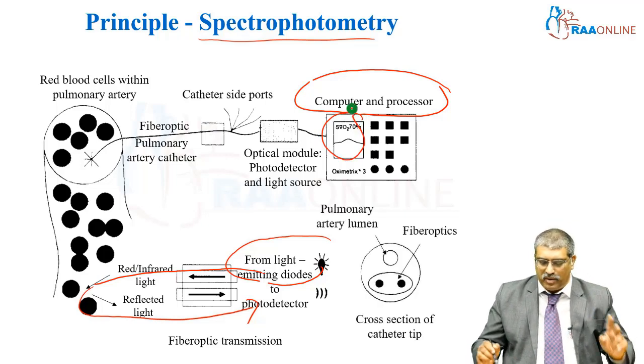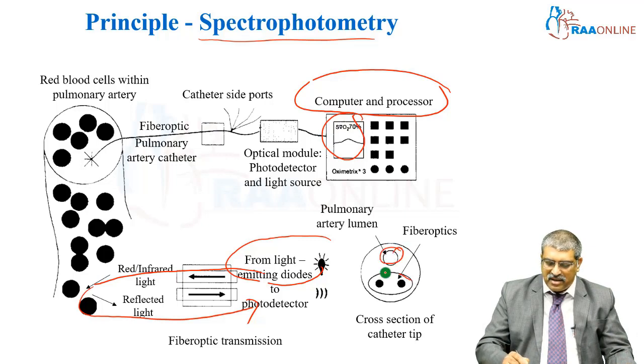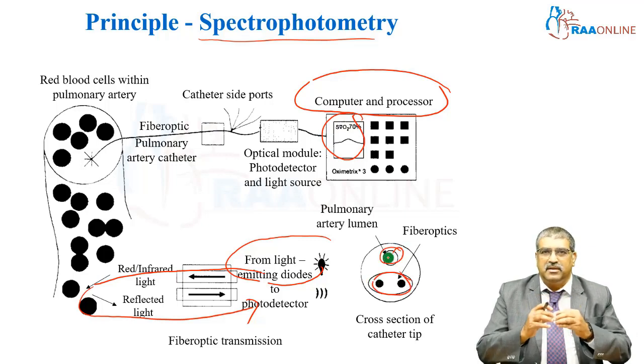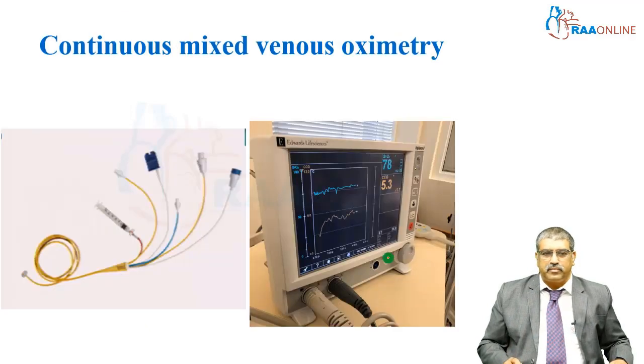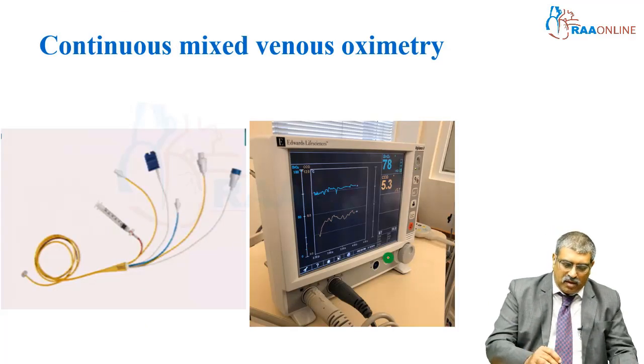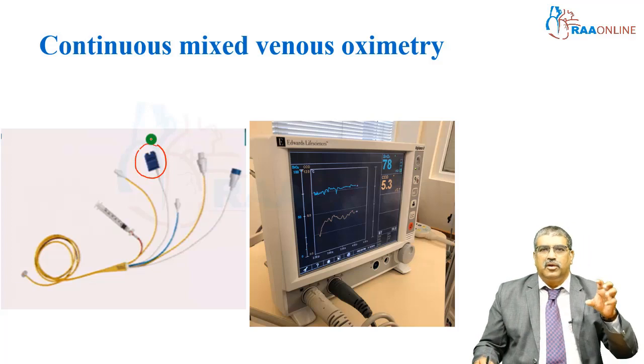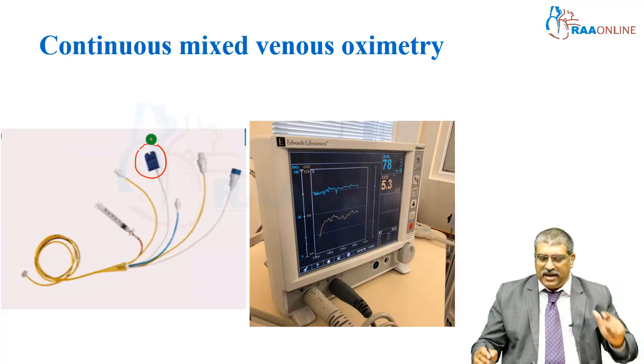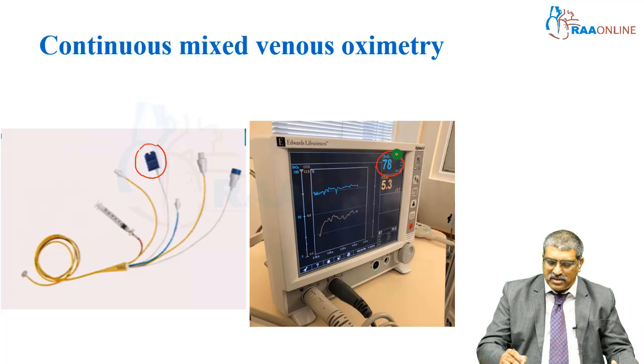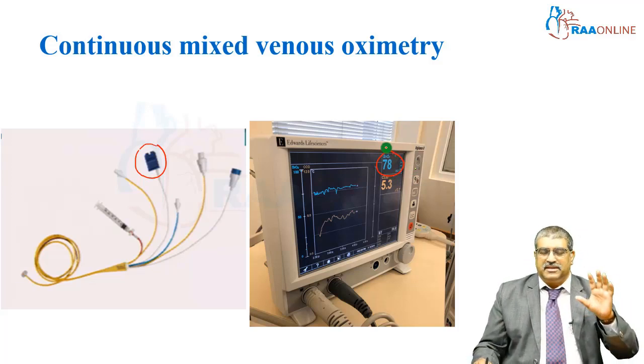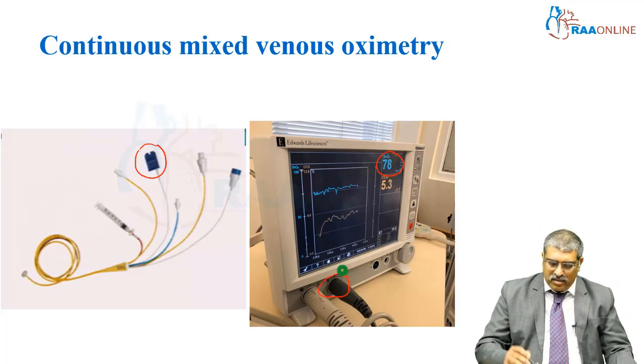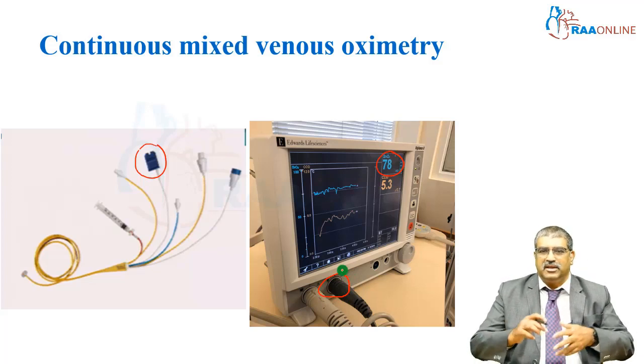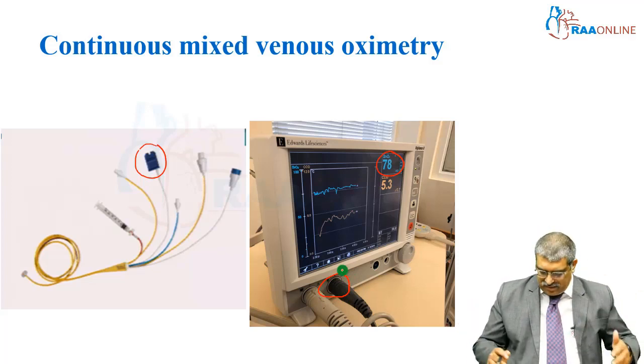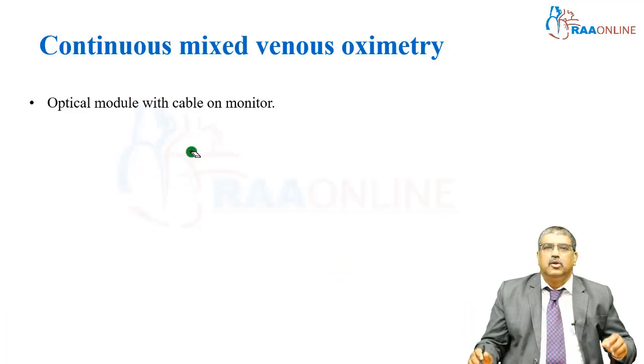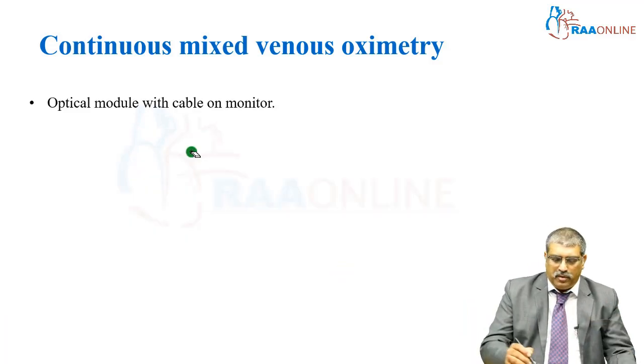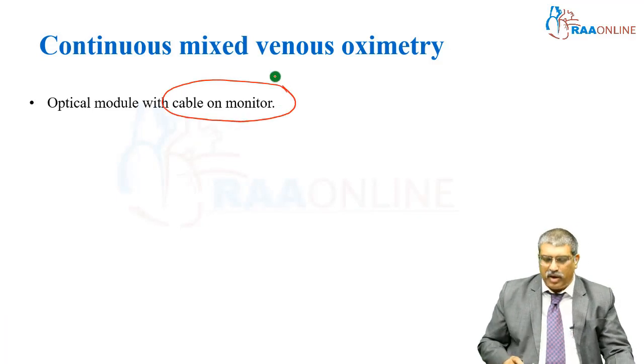So, two things are required. One is the catheter and another is the fiber optic bundle at the distal tip of the catheter. Here this is the oximetry port which sends the signal, and later it is reflected back, and here you can see the mixed venous oxygen saturation as a digital value. This is the port which is connected to the machine so that the oxygen saturation comes as a digital value. So, you have an optic module with a cable connected to the monitor.